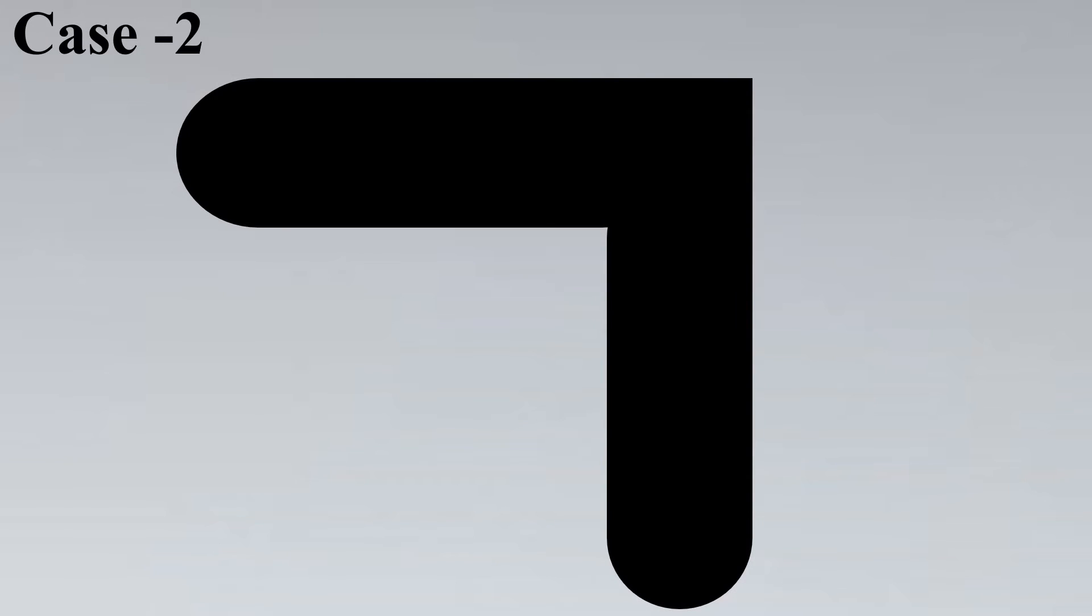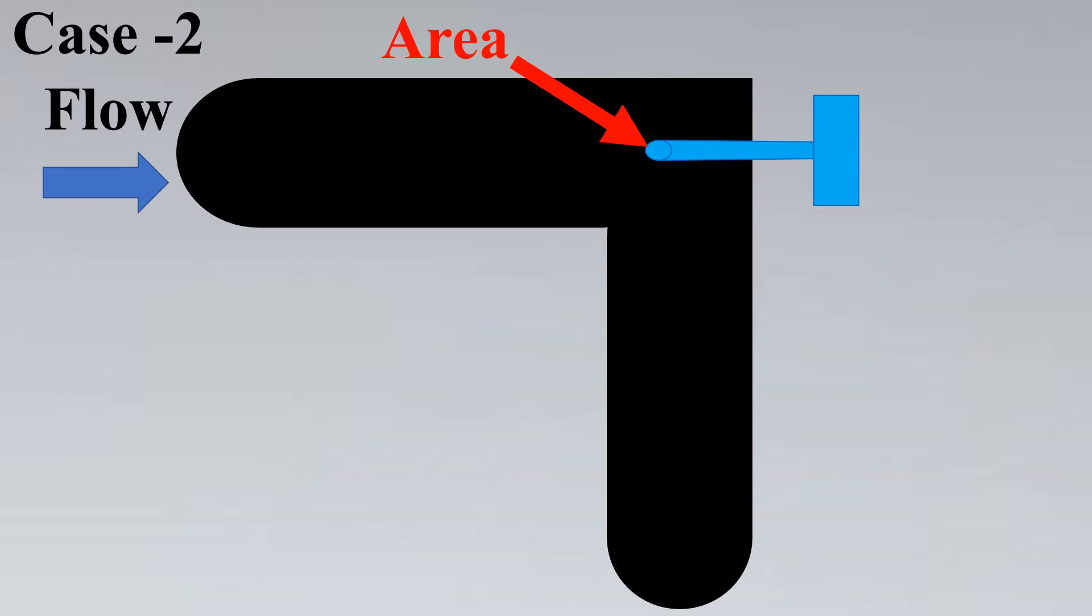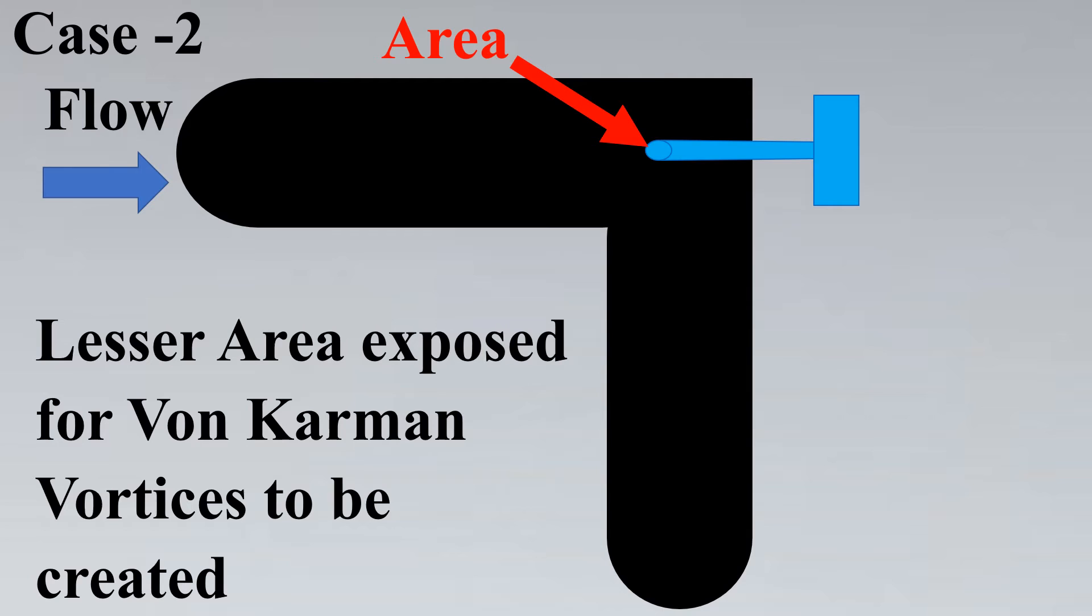Now let us look at case 2. In case 2, if you see this elbow and let's keep the flow direction same as previous case. However, we will change the installation of the thermowell. We install like this the tip facing towards the flow. Now do you see a difference? Let's see the area which is exposed towards the flow which is perpendicular to the flow. It's a very small area and thus the chances of vortex and vortices is greatly reduced and thus there would be less vibrations and thus we can significantly reduce the effect of vortex and vortices on the thermowell.